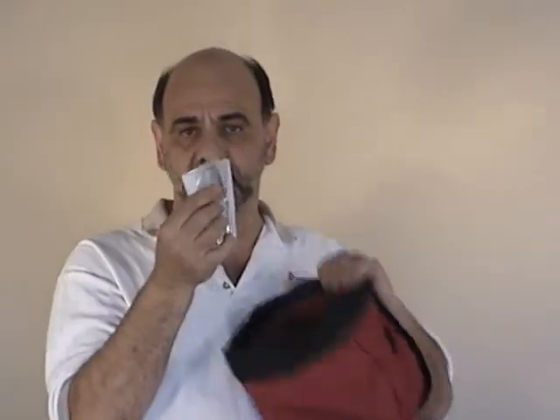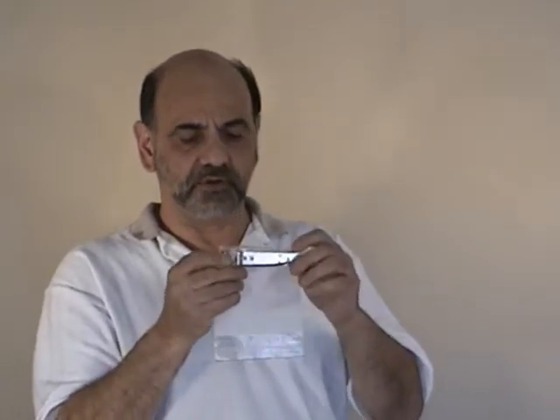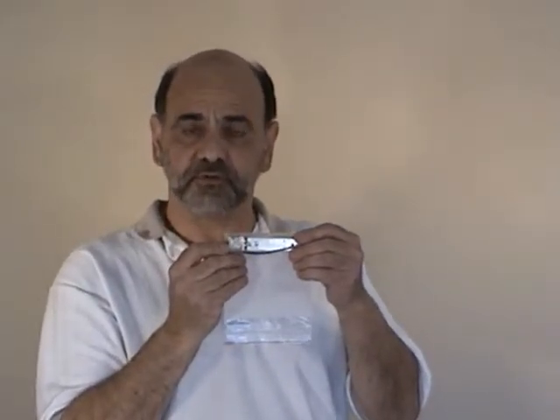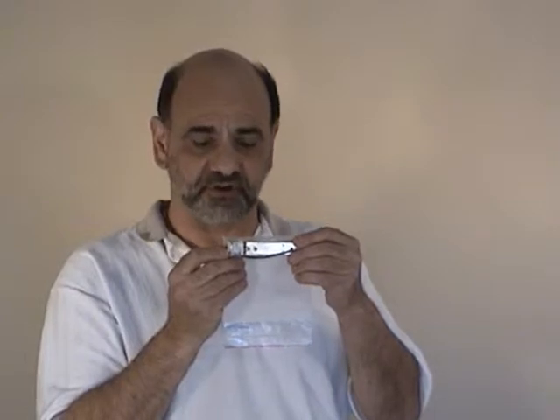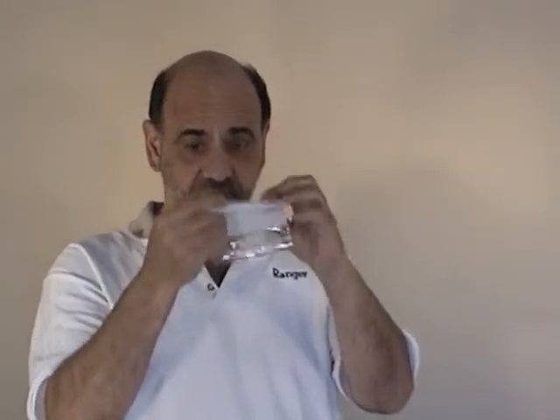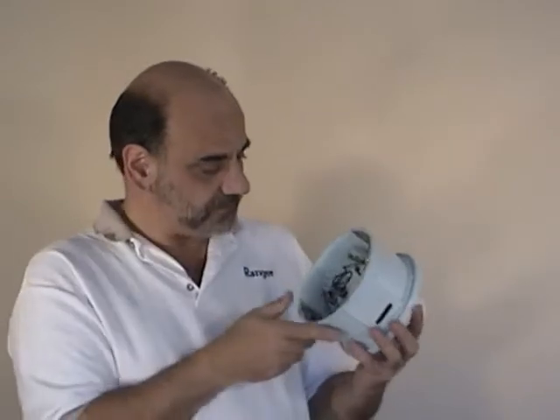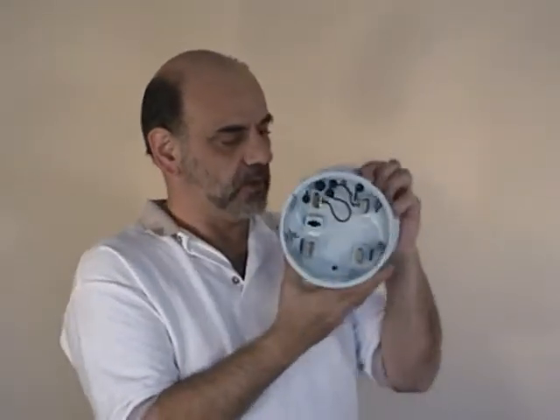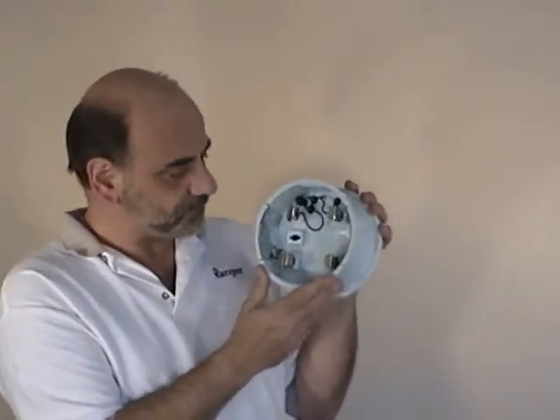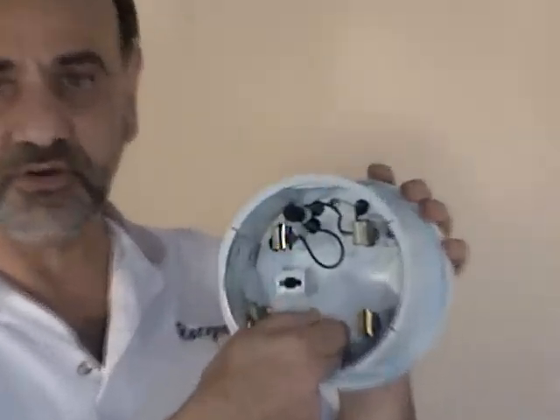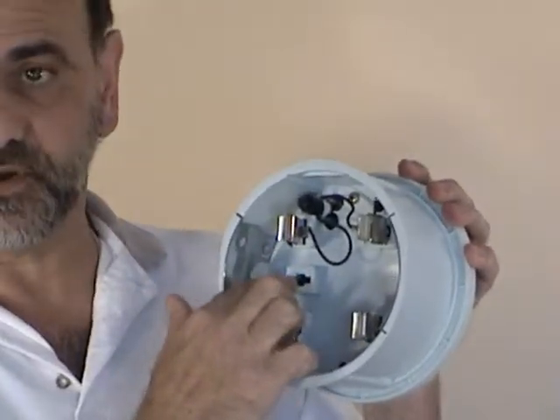There'll be a little bag in the unit. In this bag will be another neutral blade if necessary for either the 9 o'clock or the 6 o'clock position, and a jumper wire and a cotter pin. So if you do need to use these, you can. It will be in each unit. The meter socket logger itself would set in this orientation here. There will be a 6 o'clock position and a 9 o'clock position here.